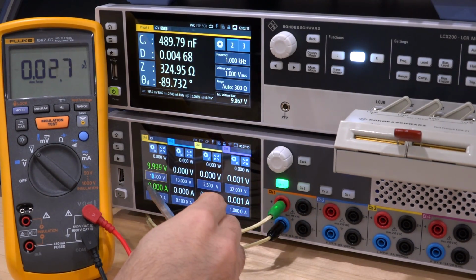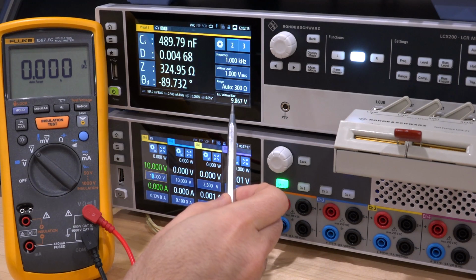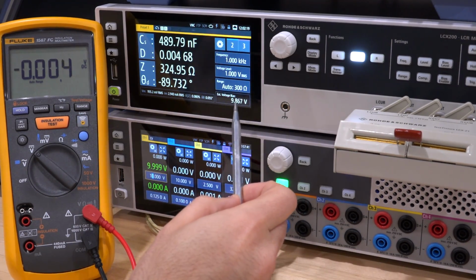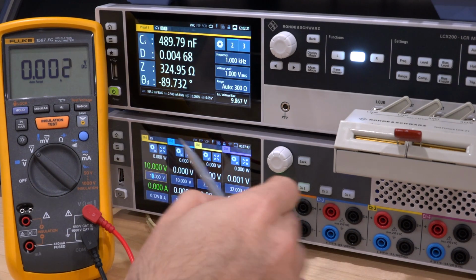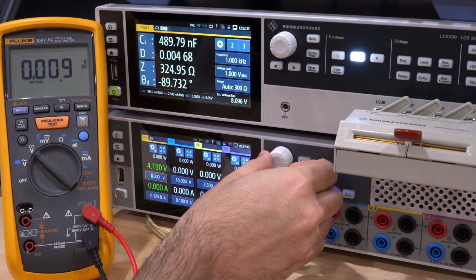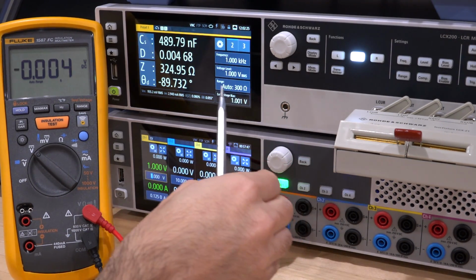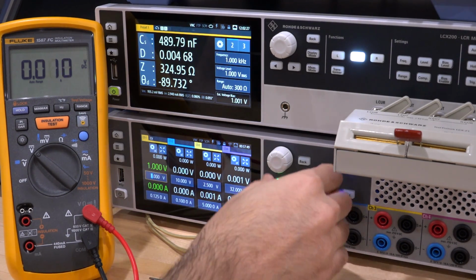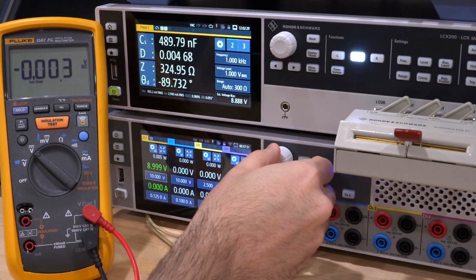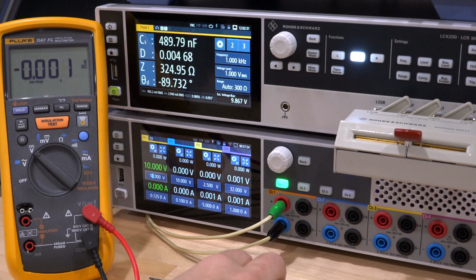Now this voltage and this voltage are not exactly the same. 9.867, this is 10 volts. Perhaps this is supposed to be within a few percent, but I noticed that this curve is a bit nonlinear, so at lower voltages, for example, if I bring this down to 1 volt, I actually do get a 1 volt reading almost exactly, but as I go to higher voltages, there's a bit of a drift away from it. I think this might be some calibration coefficients that need to be adjusted.